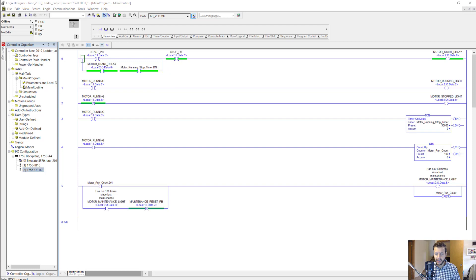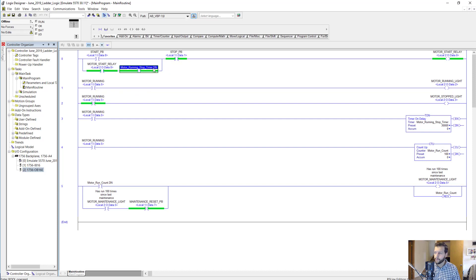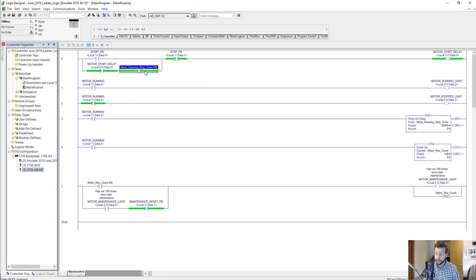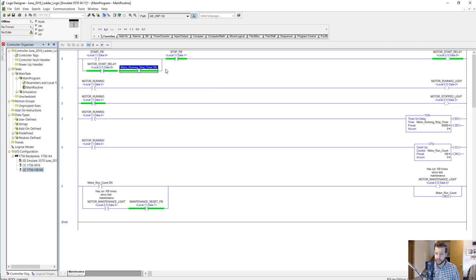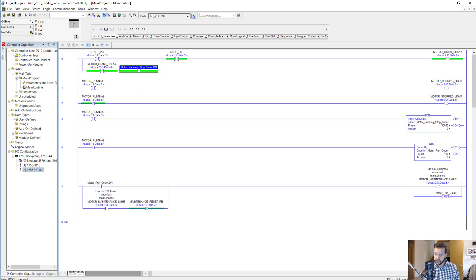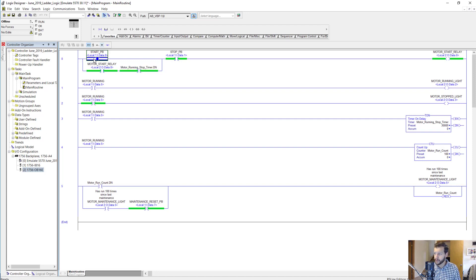This next item here will be in charge of stopping the motor or interrupting the circuit. This is an XIO which functions like a normally closed contact. When this tag, motor running stop timer dot done, becomes true, this instruction will open like a normally closed contact would and interrupt the circuit or break the seal. To start the motor again, you'd have to press the start button again.